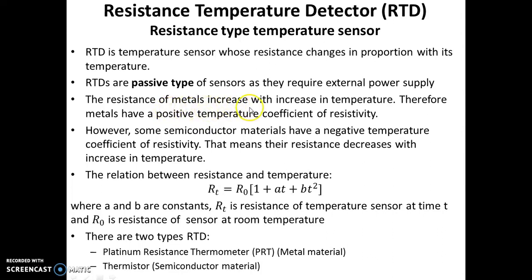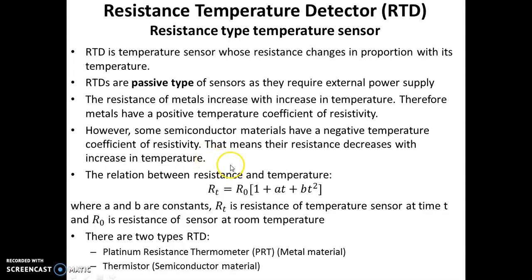The resistance of metals increases with increase in temperature, therefore metals have positive temperature coefficient of resistivity. However, some semiconducting materials have negative temperature coefficient of resistivity, meaning their resistance decreases with increase in temperature. The relation between resistance and temperature is given by RT = R0 × (1 + AT + BT²), where A and B are constants. RT is the resistance of the temperature sensor at temperature T and R0 is the resistance of the sensor at room temperature.